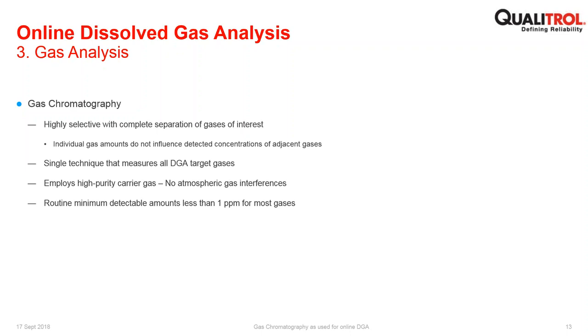Single technique that measures all DGA target gases. I mentioned there were many different techniques and many different applications for gas chromatography. For the dissolved gas analysis application, where there are 9 gases, a single detector can be used to detect all of those gases. And that again is driven by the fact that gas chromatography separates those gases. So there is no need for separate detection techniques or for other mechanisms for quantifying the gases, because you physically separate them, and that makes measurement a much, much simpler proposition.